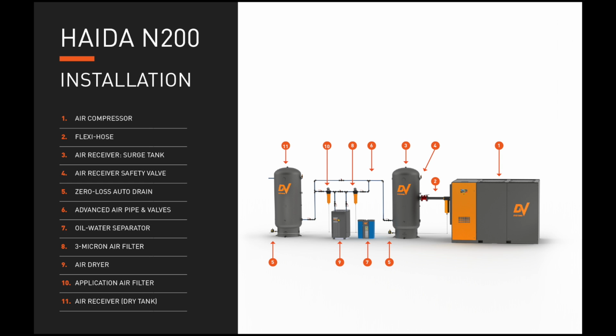Now you can't quite see it here, but we do recommend putting a cyclone filter right on the discharge of the compressor. And we have a flexible tubing here which connects to your air receiver surge tank. There's also a safety valve on the tank that would be sized to the use that you require. At the bottom of the tank, we have a zero loss auto drain. And here we have the advanced air piping. The first filter that you would use would be a 3 micron air filter. And then here you have the dryer. And then after the dryer would be the application air filter that you could get to a smaller micron filter here. You also have an oil water separator after the dryer.